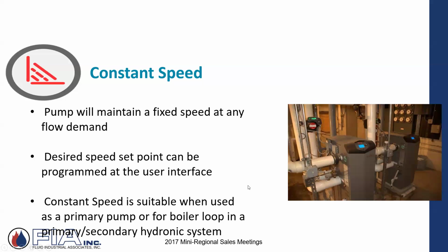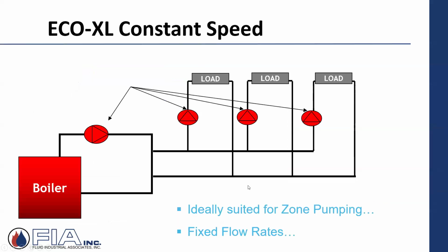Another application on that same pump is that I can do a constant speed, but you can dial it in. Just buying a pump off the shelf, you can actually configure the pump curve. What's a constant speed? It's something where you have a pump running whenever there's a call for cooling or heating, and there are no zone valves. It's a fixed load. Whenever that turns on, that's what it is. But I can dial in that pump's performance to the application, to the terminal unit.